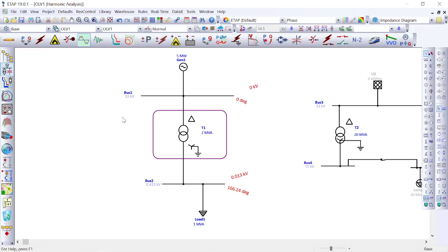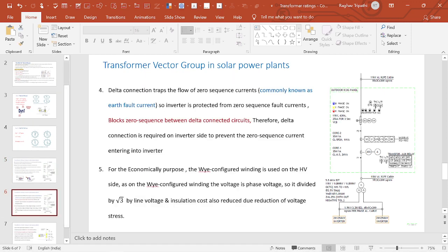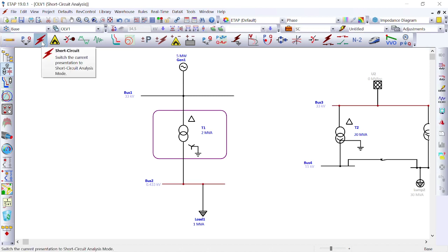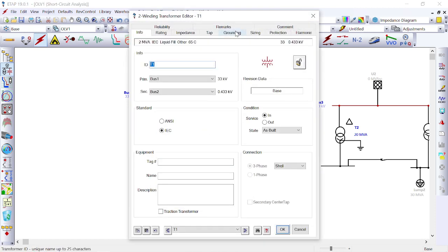The second reason why delta is used: zero sequence current. Delta connection traps the flow of zero sequence current, which is normally called earth fault current. The inverter is protected from zero sequence fault current. The delta winding blocks zero sequence current between the delta-connected circuits, so the delta connection is required on the inverter side to prevent zero sequence current from entering the inverter.